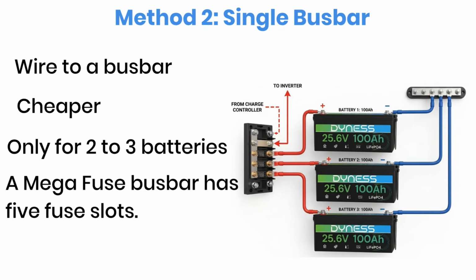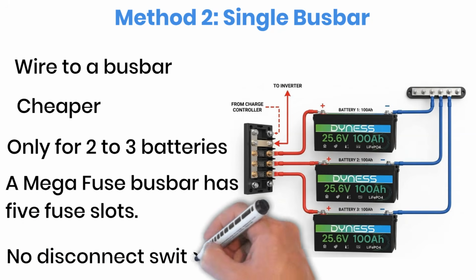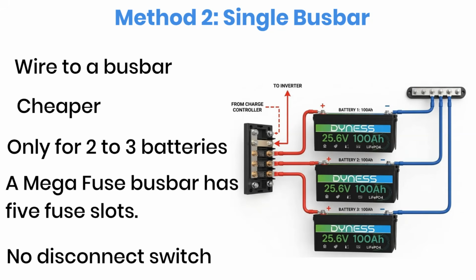Another thing to keep in mind is that this arrangement usually doesn't include a single disconnect switch for the entire battery bank. If that's something you want, you'll need to add a properly rated breaker or battery disconnect separately. Now let's look at the third wiring method, which is generally the better choice once your battery bank starts growing.